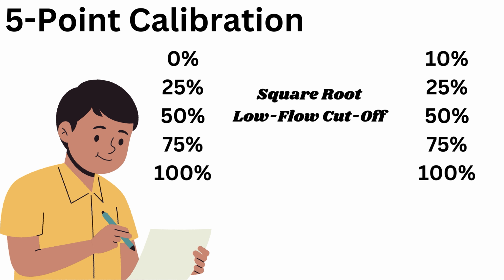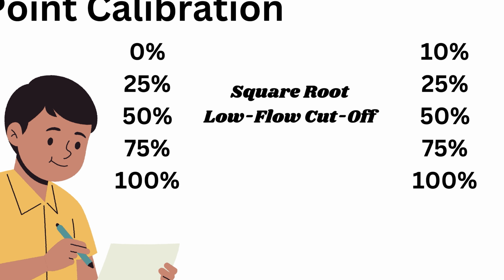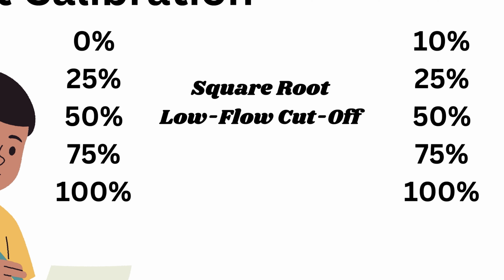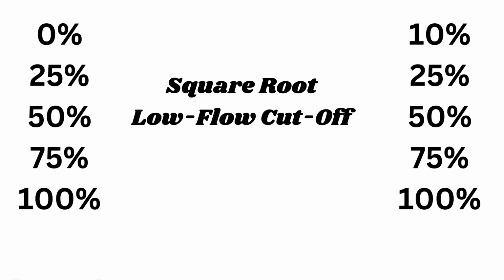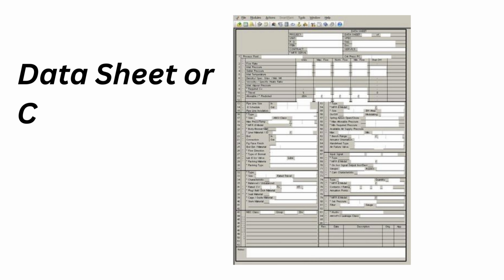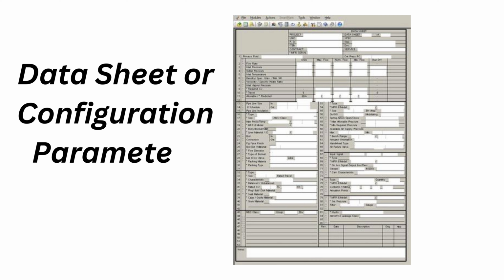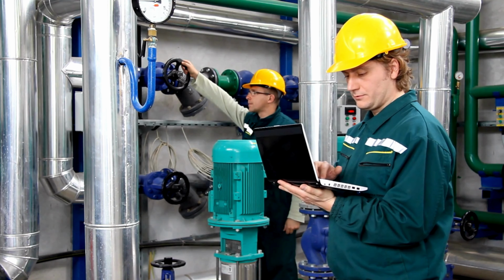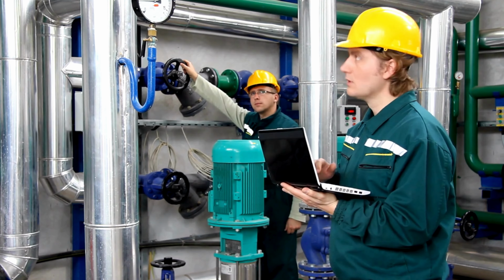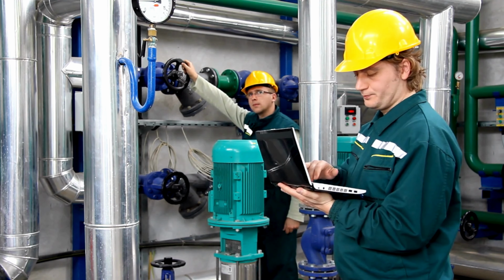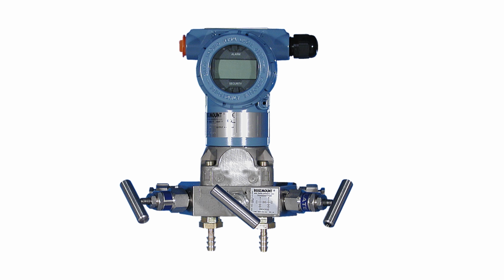Calculate the errors, the differences between digital voltmeter readings and reference pressures, as the pressure is increased from 0% to 100% and decreased from 100% to 0%, and confirm that the errors are within the required accuracy. Adjusting calibration settings. If you notice discrepancies, adjust the calibration settings until the output matches the input accurately. After calibration, double-check all your connections. Ensure there are no leaks and that the wiring is secure. And that's it. You've successfully installed and calibrated a differential pressure transmitter.